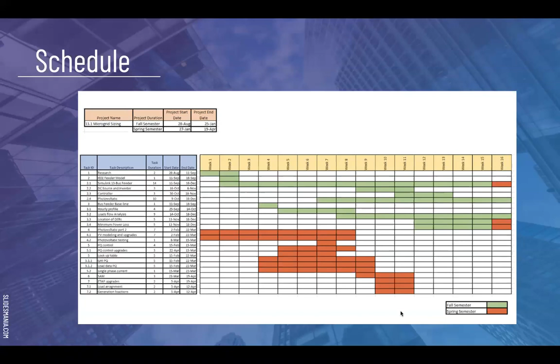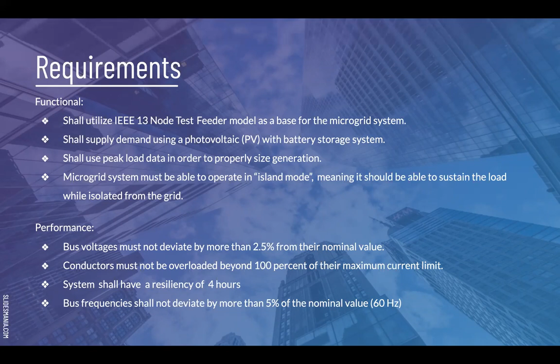For our requirements, we want to have a functional 13 bus node feeder as a base for the microgrid. We also want to supply the demand using a photovoltaic with battery storage, as well as use the peak load data in order to properly size the generation. With the microgrid system we must be able to operate in island mode, meaning it should be able to sustain the load while being standalone. For performance, we want bus voltages to not deviate more than 2.5% from the nominal value. Conductors must not be overloaded beyond 100% of their maximum current limit. The system shall also have a resiliency of 4 hours. Bus frequency shall not deviate by more than 5% of the nominal value.